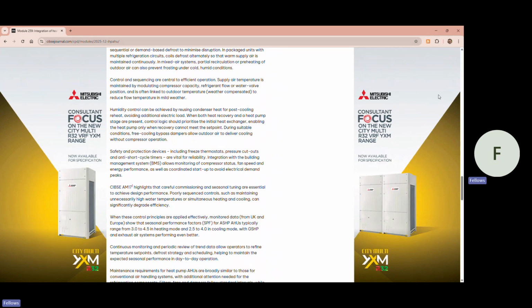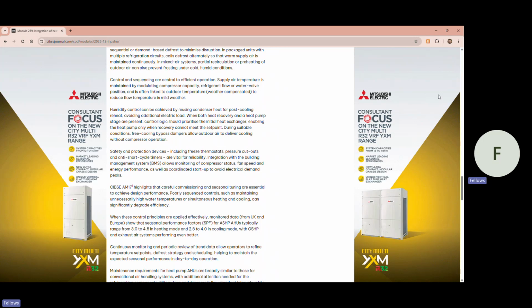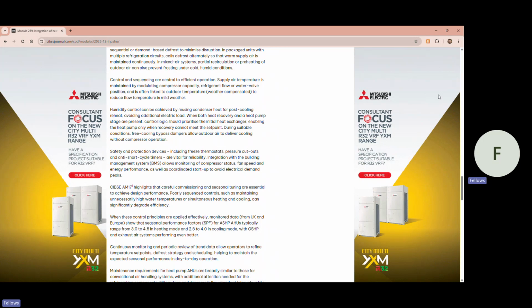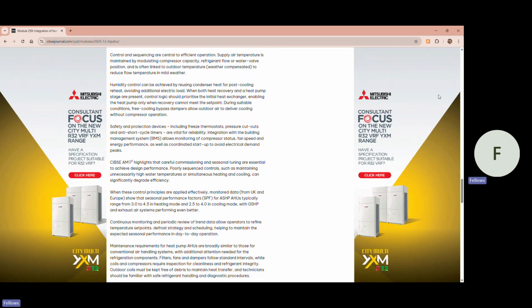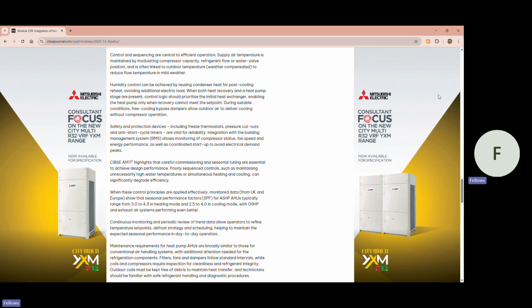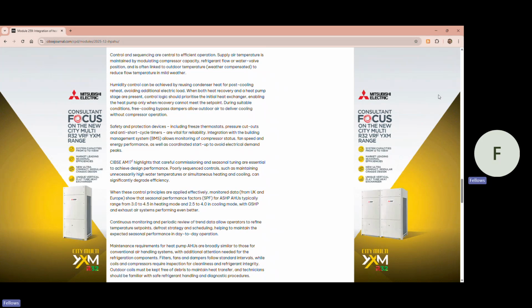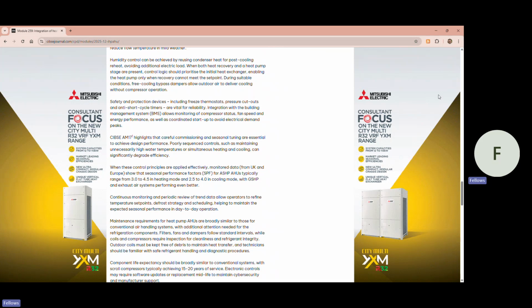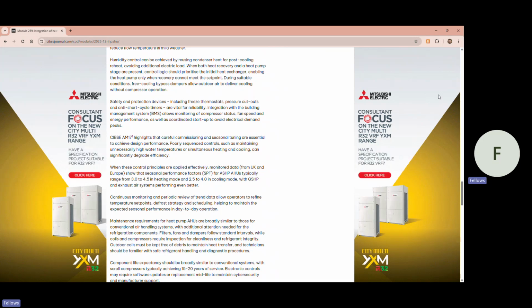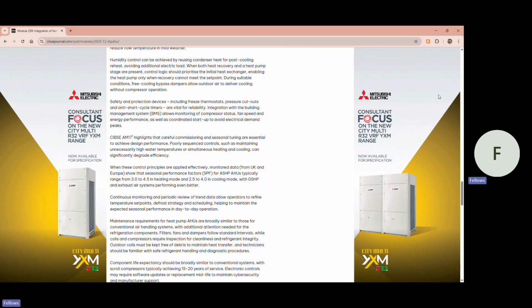Integration with the Building Management System, or BMS, allows monitoring of compressor status, fan speed, and energy performance, as well as coordinated startup to avoid electrical demand peaks. CIBSE AM17 highlights that careful commissioning and seasonal tuning are essential to achieve design performance. Poorly sequenced controls, such as maintaining unnecessarily high water temperatures or simultaneous heating and cooling, can significantly degrade efficiency.